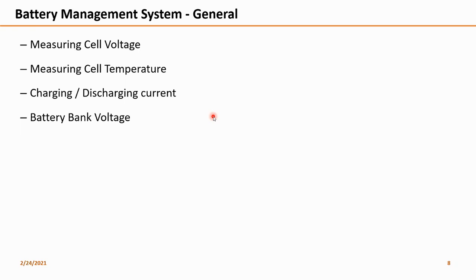So this is a major point where we need to monitor the cell voltage. Parallelly, we need to know the battery bank voltage, because numerical relays or motors which we have operate on specific voltages. So as battery is an emergency system, this also needs to be monitored closely.